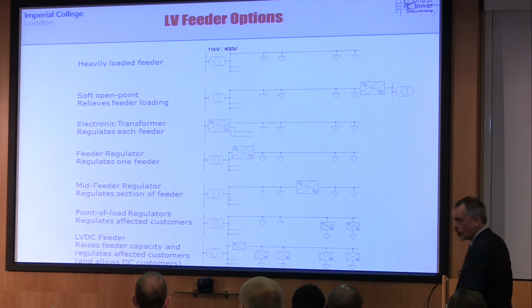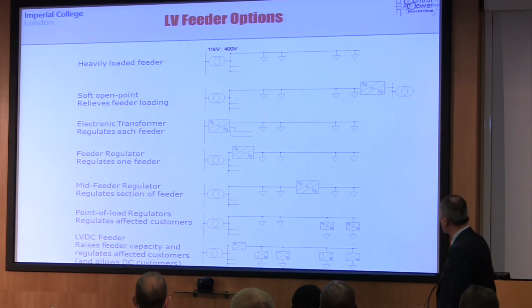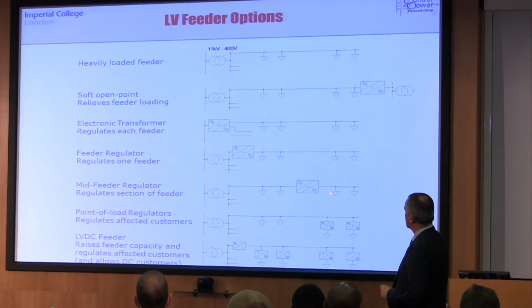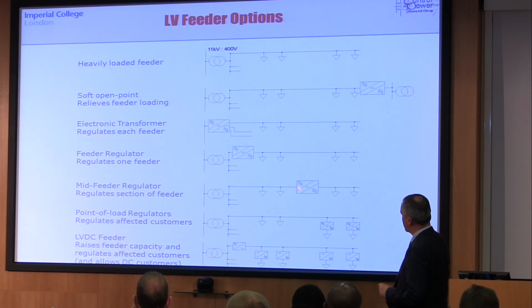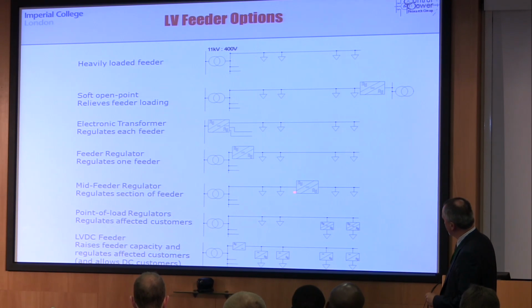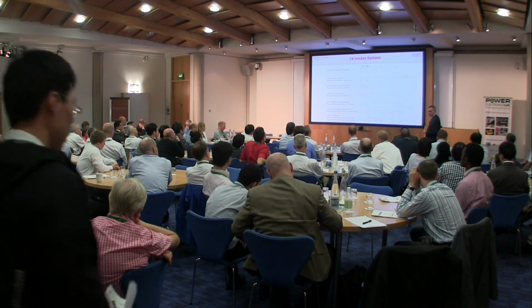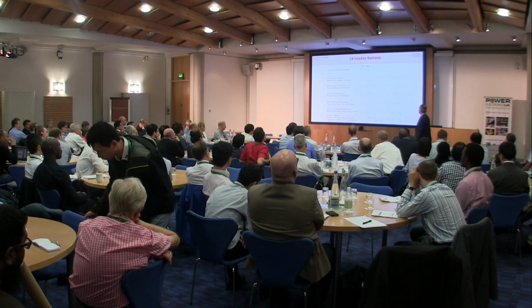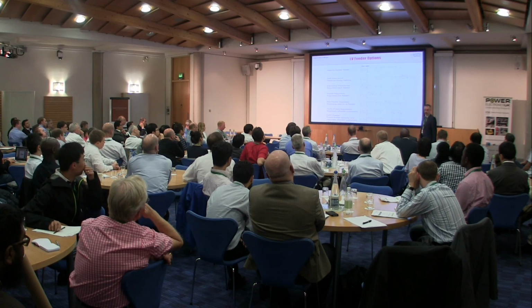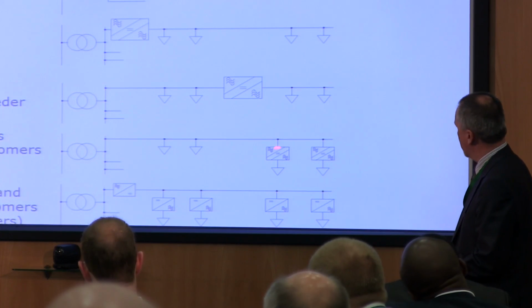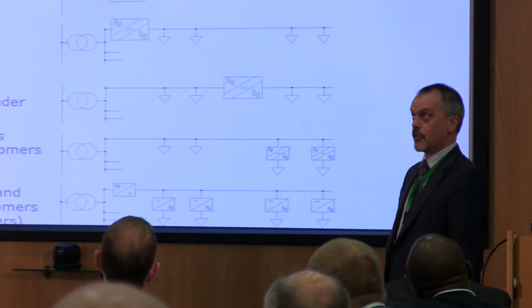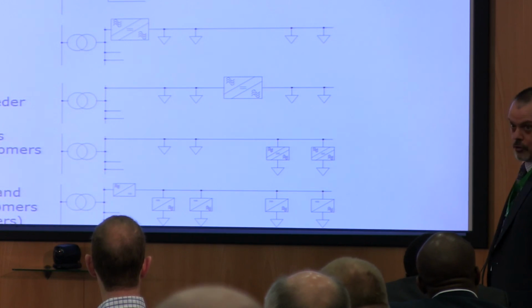Or if the problem is only one feeder, perhaps we just need to put a much smaller rated converter on one feeder. But often if the problem is about voltage, its far end of the feeder is the problem. So maybe we can further reduce the power rating of this device by putting it mid-feeder. This end of the feeder is largely okay. It's this end that is going to rise or fall, so do some voltage injection or voltage manipulation partway down the feeder. And perhaps the next step of that line of thinking is, well, why don't we just address the customers who have a problem and put point of load regulation in? Put power converters on the entrance to a house or a group of houses where there's a problem.